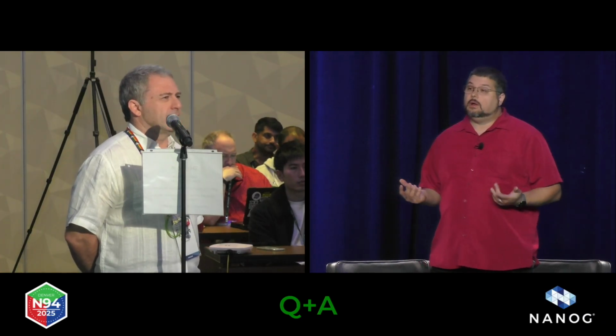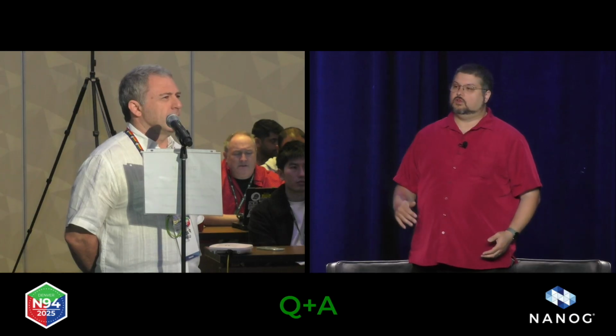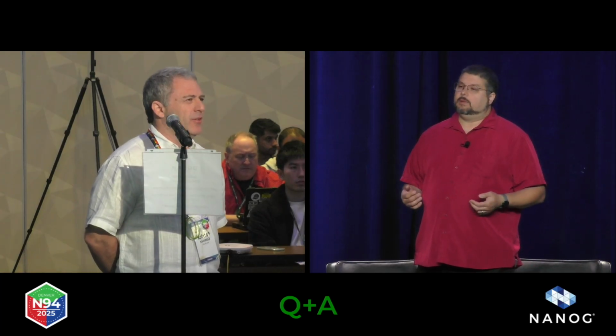So for those unfamiliar, in Open Rack standards, 1OU is both wider and taller than an RU. In our data centers, that's a reasonable footprint because all of our racks are Open Rack, but in POPs, we use industry standard 19-inch racks. In fact, many of our racks in POPs don't even have roofs on them in which to mount the PON canopy. So to that end, no, we would expect in POPs to go in with an RU device. And do you see any problems with that?